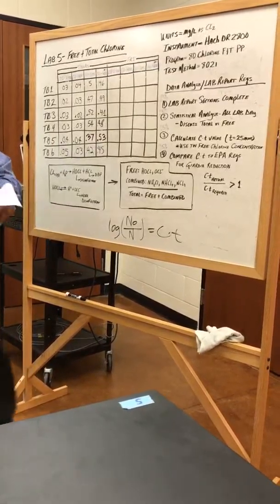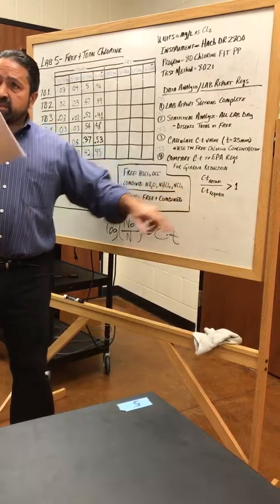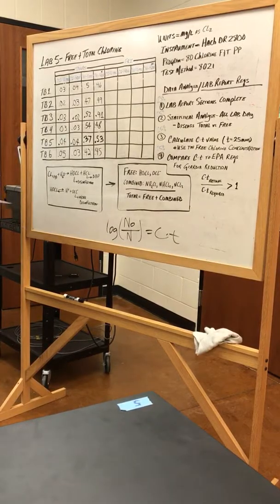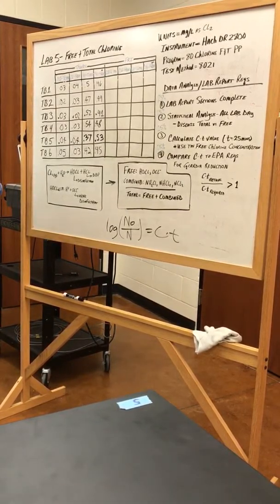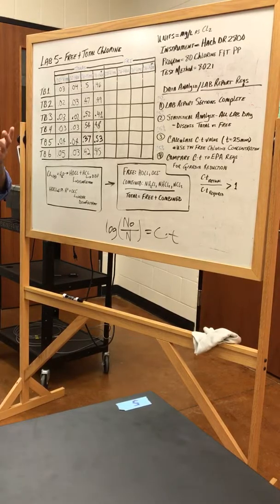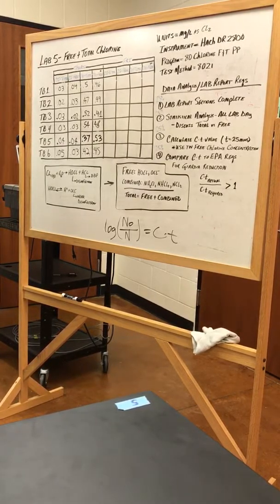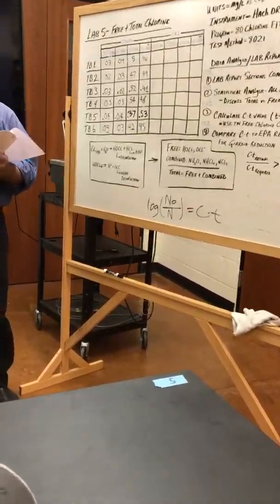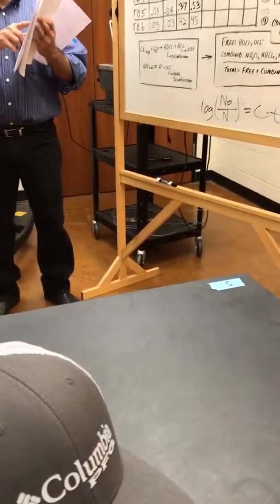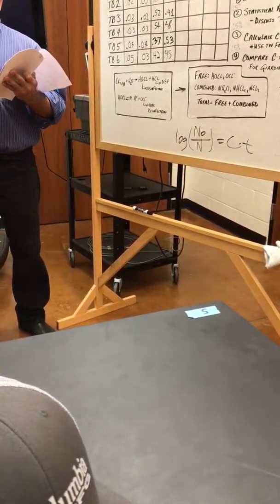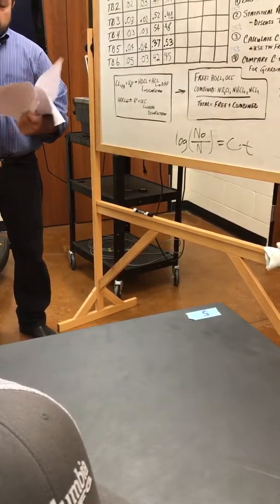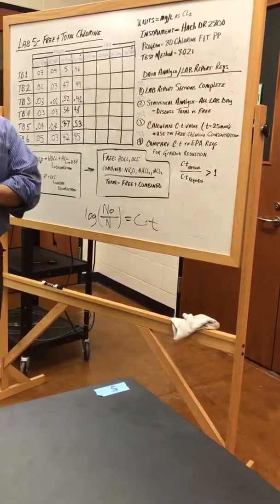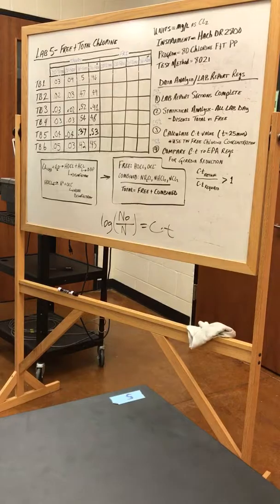Once you have that, you need to get your required CT value. As Dr. Thomas mentioned, it's all given here. Based on the fact that this is Giardia that we're looking at, there's a 3 log reduction requirement, but we're assuming there's a 2.5 reduction credit already given through filtration and other processes. So all we're looking at is a 0.5 log reduction. That 0.5 is given as 12.3 milligrams per liter. Actually, that's a CT value already with the time embedded in it. That already has the 25 minutes in there.